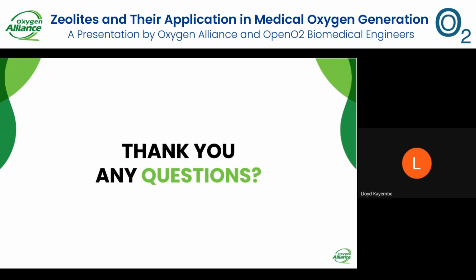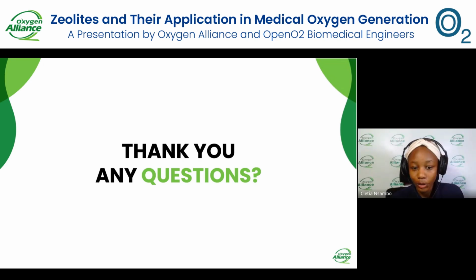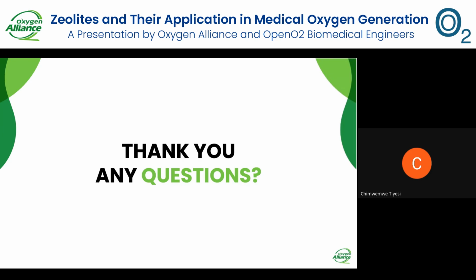Over to you, Apostle. It's basically what Lloyd has said. Our test concentrator for the zeolite that we regenerated has been running for more than 5,000 hours, still producing above 90% oxygen purity. It's still going. Just to add on to what Lloyd said.